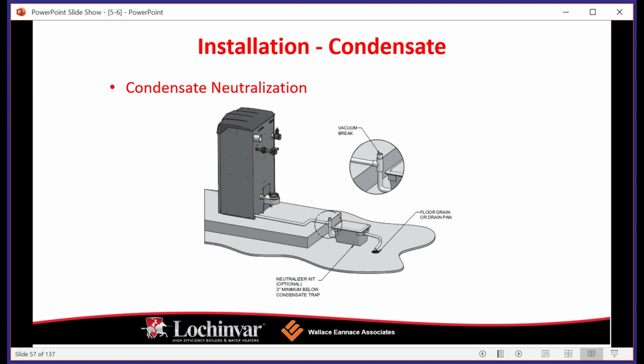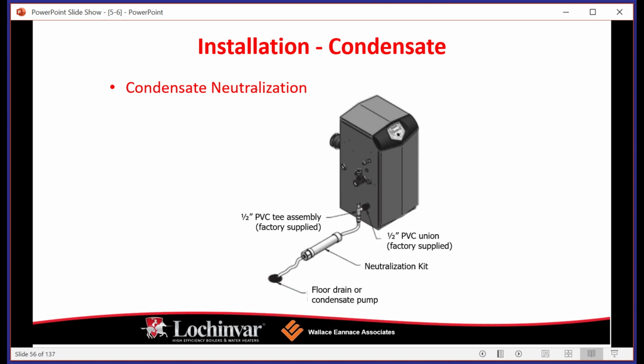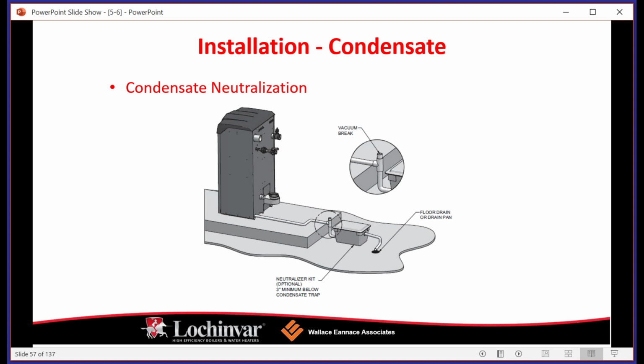Okay, here's another condensate neutralizer. The one we saw in the previous slide was a cylindrical neutralizer, and this one is more of a kind of a bucket, right? A rectangular box. The difference between the two is basically the volume of the media that's in there. How much of the rocks or those little pebbles do we need in order to counteract the amount of condensate that's flowing through it? So we got a smaller boiler. It's going to use a smaller cylindrical neutralization kit, and a larger BTU input is going to require a neutralization kit that's shaped more like a little box, and it's going to hold more volume and allow more condensate to be neutralized.